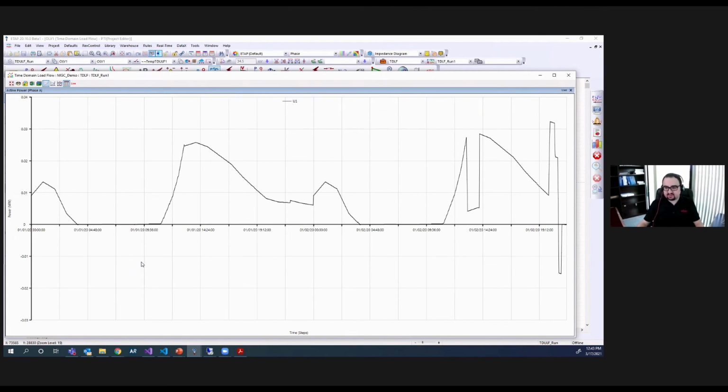Basically, the job of the Microgrid controller on the first day, when the system is connected to the grid, is to do economic dispatch analysis and dispatch the assets in the system to reduce the cost of operation. So you can see that we are importing power from the utility, but we are limiting the export power to the utility. As you can see, there is no export power, because I will show you in the battery inverter that during this time we are charging the batteries.